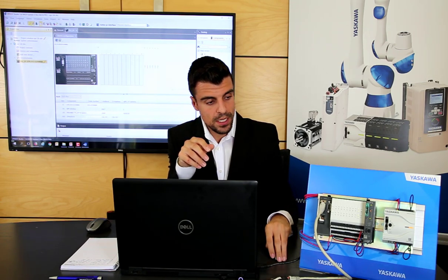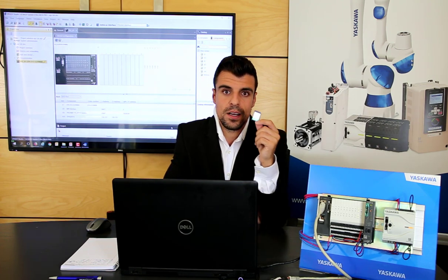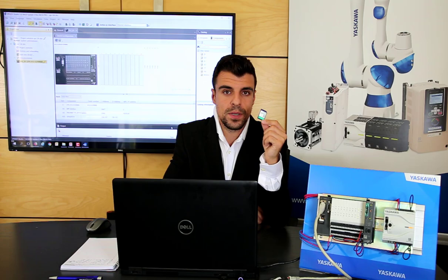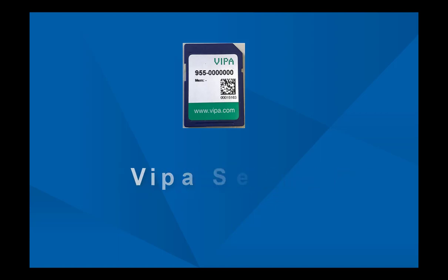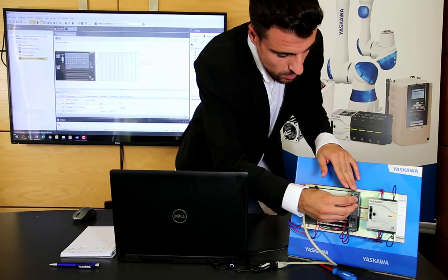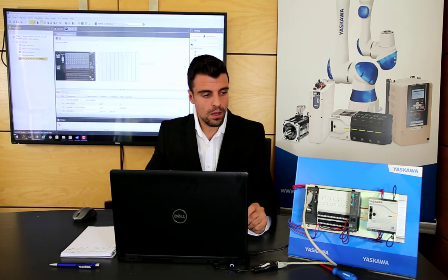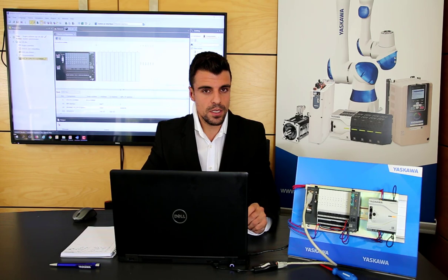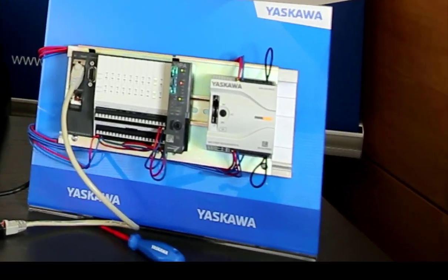The next step is that we can use the OPC UA. We need a SD card, a feature set card. Insert the SD card in the slot of the SLIO PLC. And at this point it is important that it's not enough only to insert, we need to make also an overall reset.